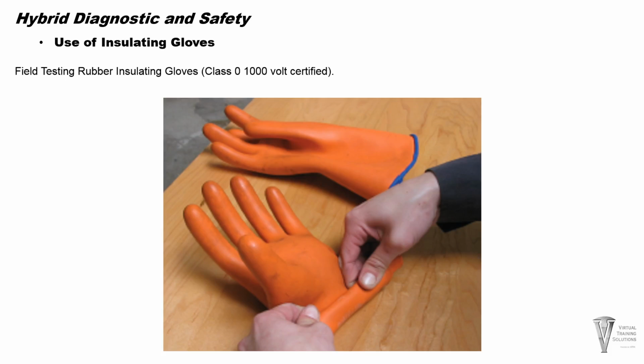Roll the cuff towards the fingers to inflate the glove as much as possible without allowing any air to leak. You can damage the glove even if it's in good condition by doing this, so be very careful. Once you've reached a point where it's tight and it's not leaking, you're good. Listen for air leaks and watch the glove for any signs of deflation. Put the inflated part of the glove, fingertips and palm, close to your face and feel for any silent leaks. Insert the working area of the glove under water and check for bubbles. Do not allow water to enter the inside of the glove. Allow the glove to completely dry before usage. Repeat the test sequence for other gloves as necessary.